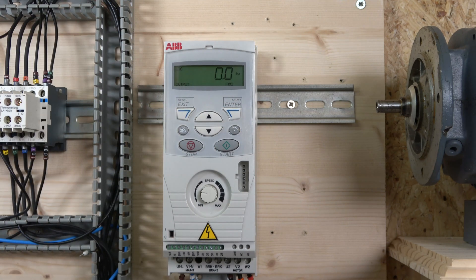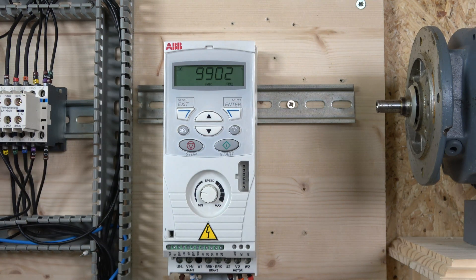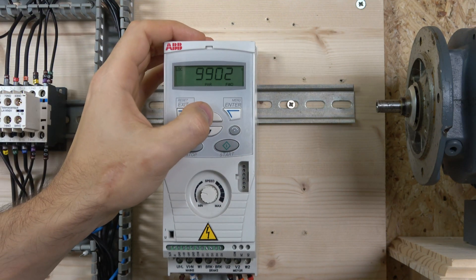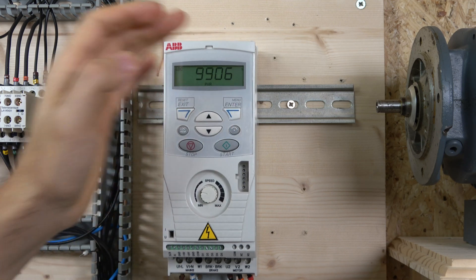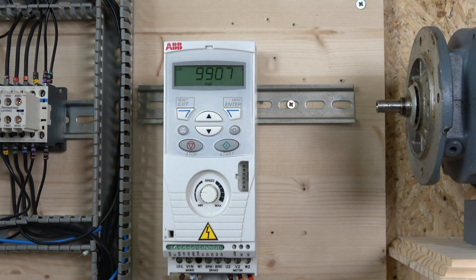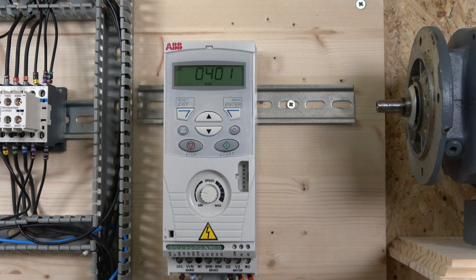Now let's start setting up the drive through the short parameter group. The first parameter is the macro group — we won't touch that today as we're doing a local run. Next is parameter 9905: motor rated voltage — set to 230 volts for my motor. Then motor rated current — mine is 1.9 amps, already entered. Next is motor rated frequency — 50 Hz.